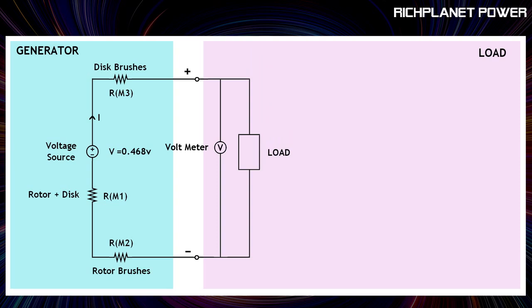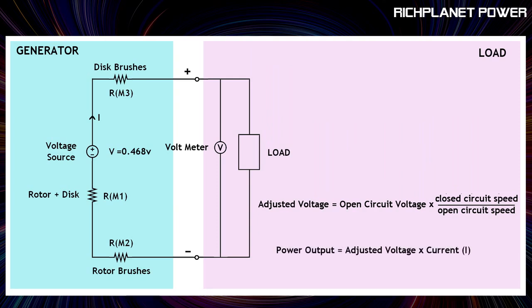A slight adjustment needs to be made with this machine, however, in that when the load is added, the induction motor speed decreases very slightly, typically about 0.2%, and hence the voltage output will decrease by this exact same amount. So in order to calculate the output voltage when the machine is loaded, we take the open circuit voltage and multiply that by the ratio of the closed circuit speed to the open circuit speed.